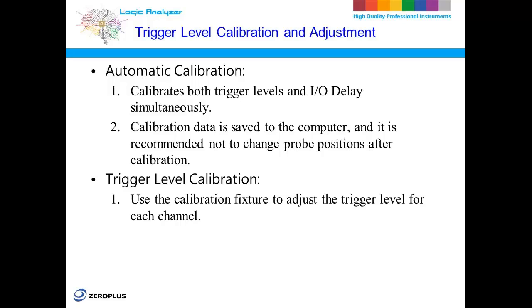Once the calibration is complete, the measured data is automatically saved to your computer, so you can keep the same calibration results for future measurements. Tip: after finishing the automatic calibration, it's best not to move the probes to a different position, because any changes might affect the previous calibration and cause measurement errors.